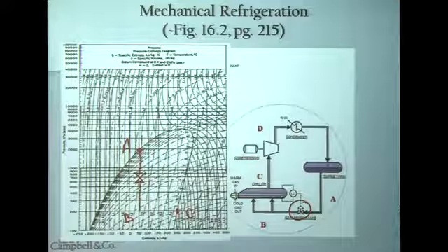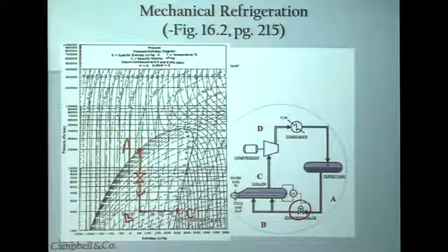You couldn't read the pressure drop on a pH diagram anyway. This is point B. So I've just taken a pressure drop through the JT valve to point B, and you'll notice that in this pH diagram, I am a two-phase mix. I have vapor and liquid at point B, which is indeed the case. I then go through the chiller. This is my chiller, and I'm going through the chiller. I'm boiling the propane. I end up at point C, which is a dew point vapor.